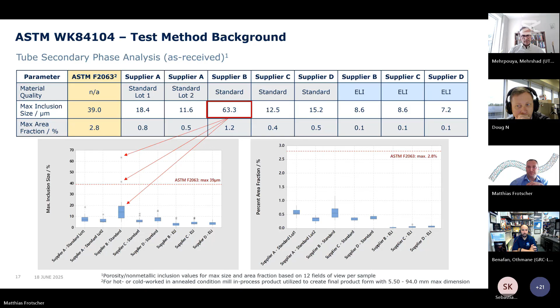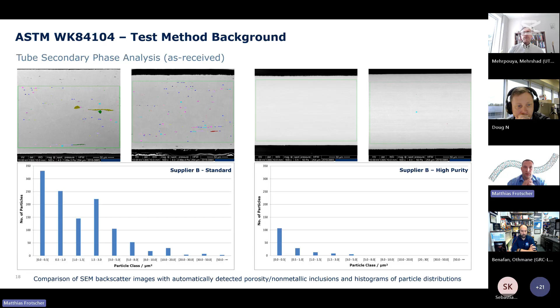These examples compare automatic image analysis of a standard and a high purity Nitinol material with the corresponding histograms of the inclusion distributions. You can see that the difference in inclusion size density becomes already obvious when looking at the SEM micrographs, but now with the new method, they can be quantified using the new methodology.